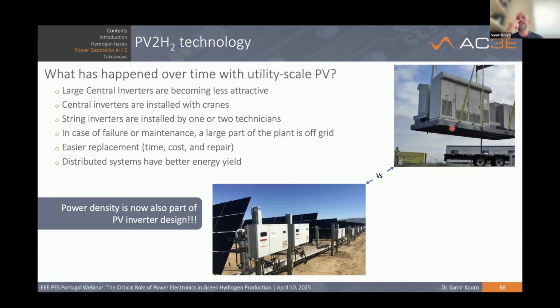The Chinese, particularly Huawei and Sungrow, detected this issue, and instead of building centralized huge inverters with economies of scale for bigger, more efficient units, they went into multi-string and string solutions, making it more modular. The problem with going modular is that you end up with a higher cost per kilowatt for the same amount of power.